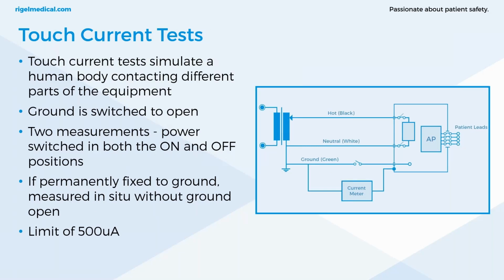Touch current tests simulate a human body contacting different parts of the equipment. That's any current that will flow from an individual, from the equipment and chassis, or any type of accessible part not intended for patient treatment, no patient leakages or patient applied parts. This is during normal operation. It applies to all portable medical electrical equipment, and unlike IEC 60601, there are no fault conditions introduced, except that ground is open. The ground is open, but there's only one fault condition that's introduced.